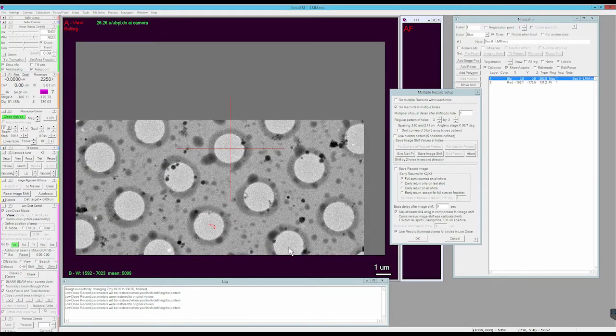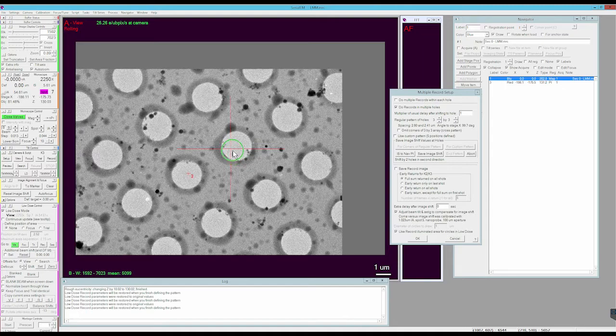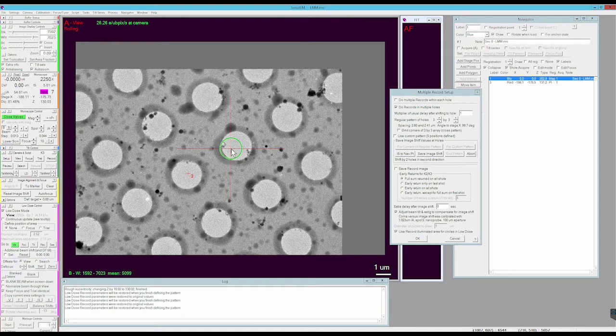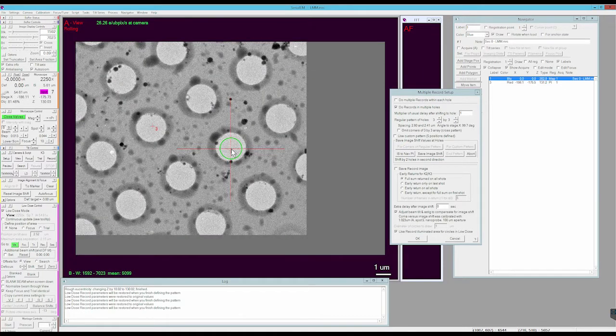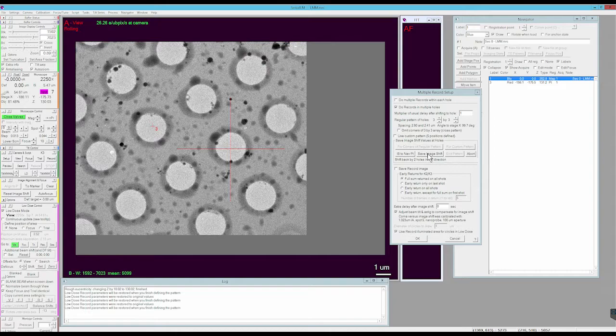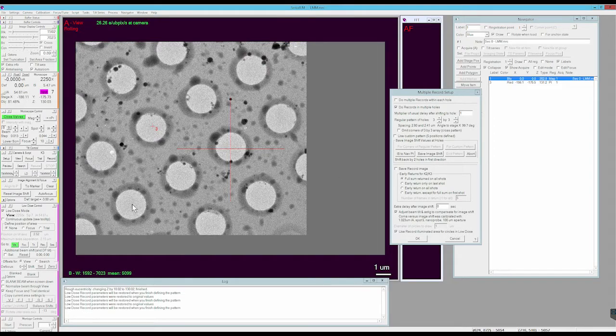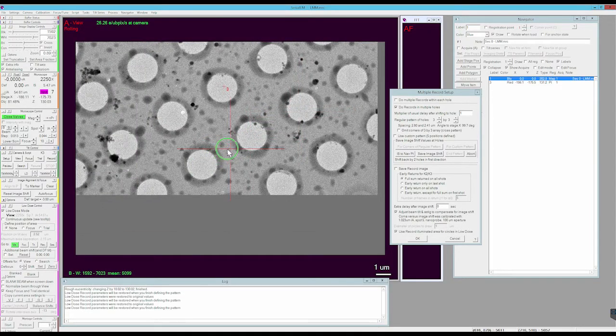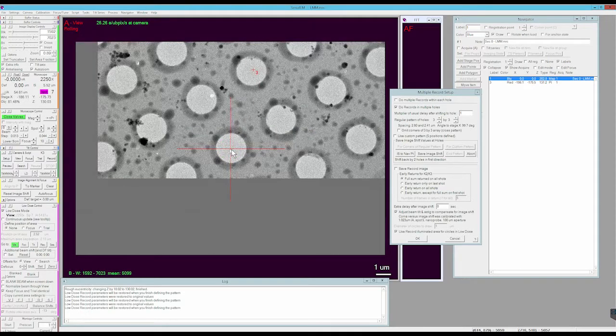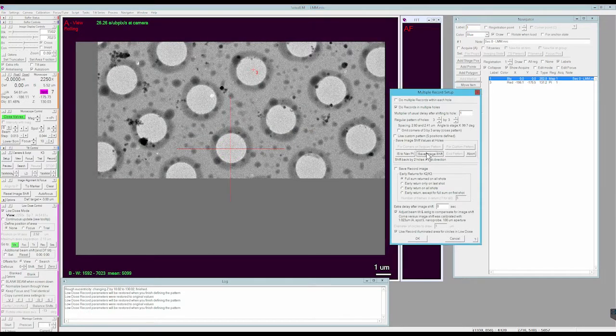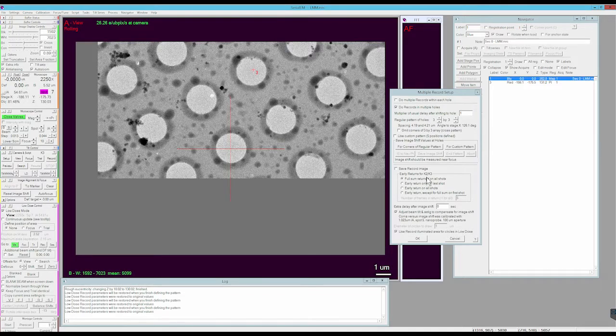Followed by the bottom right: click, drag, release once it catches up, save image shift. And then finally the bottom left: click, drag, release, save image shift. Now my pattern has been calibrated.